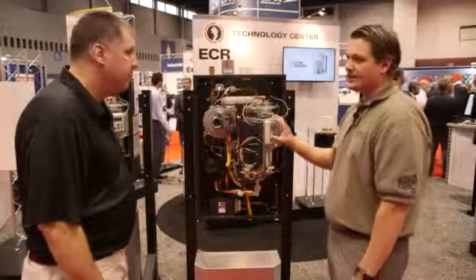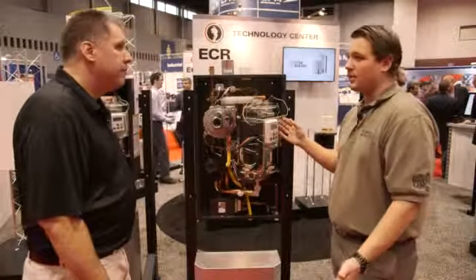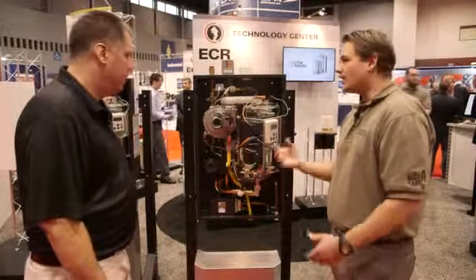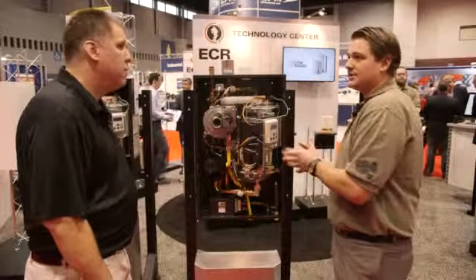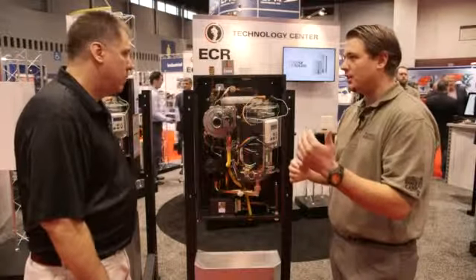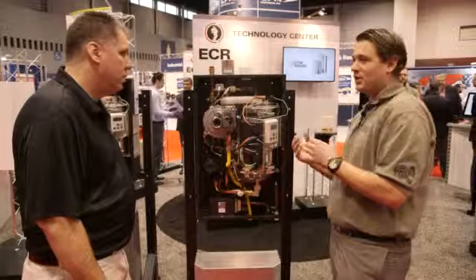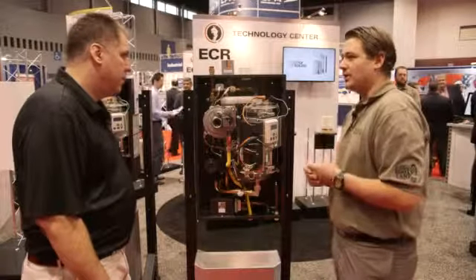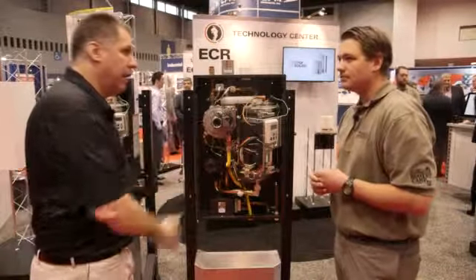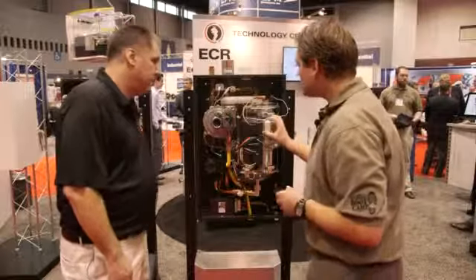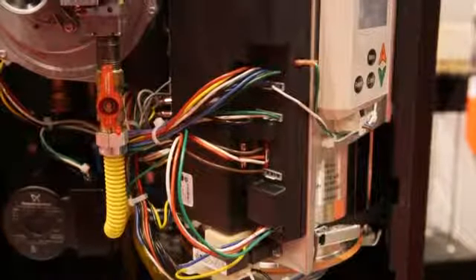Our outdoor reset is really designed around baseboard, because that's the majority of the market. Right. If you wanted to go to a radiant system, you can adjust inside the control to max it out at 120. Or maybe you have a hydrocoil system where you want to go higher on the bottom end. You can do that as well. And how high can you go with this boiler? What temperature? You can go up to 196 is the max setting on it.